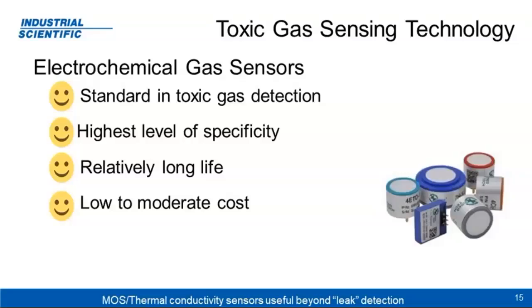Let's turn our attention and start talking a little bit about toxic gas sensors. The standard for toxic gas sensing today is still the electrochemical sensor. These sensors bring the highest level of specificity to toxic gas detection. They're not completely specific, but when we're talking about combustible gas sensors that have very broad-based detection and will detect almost anything in some cases, electrochemical sensors for toxic gas have a really high level of specificity. They bring relatively long life. I just saw the other day an H2S sensor that was alive and working in an instrument that we have not made since the mid-90s.